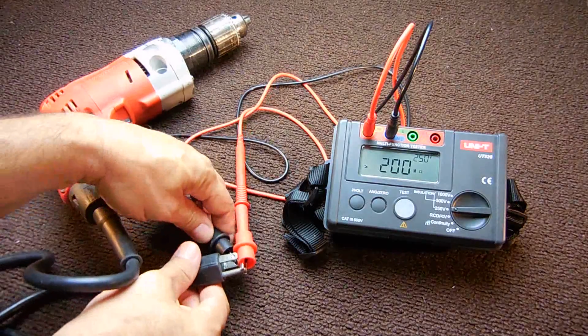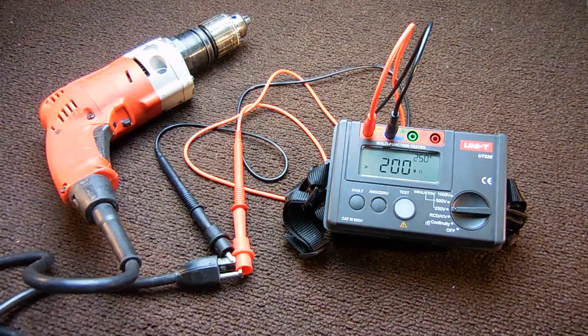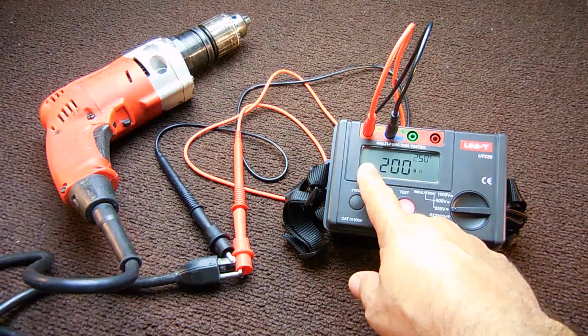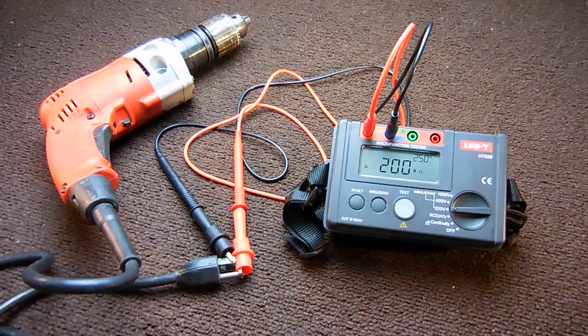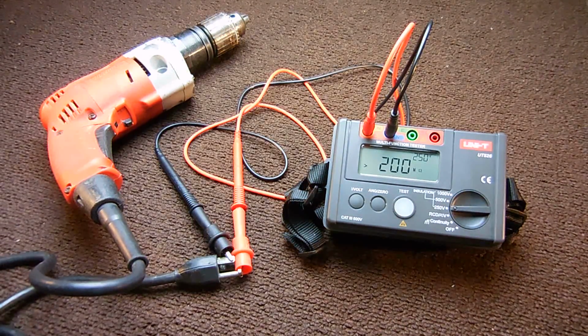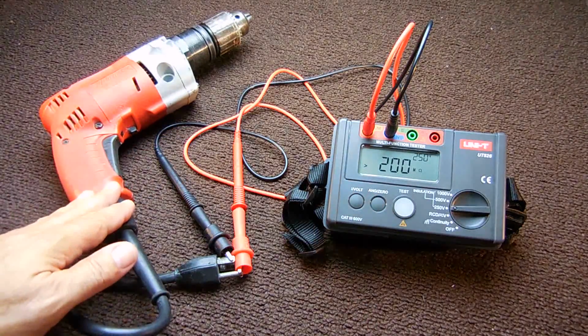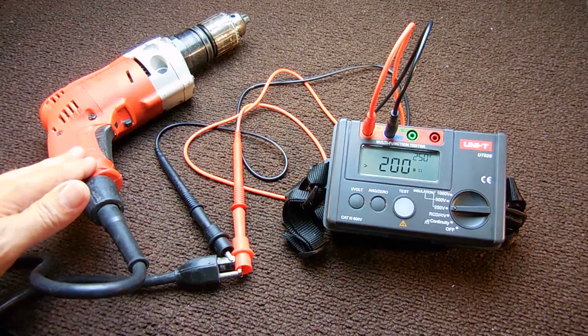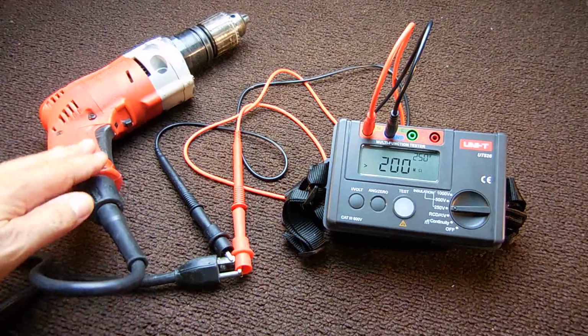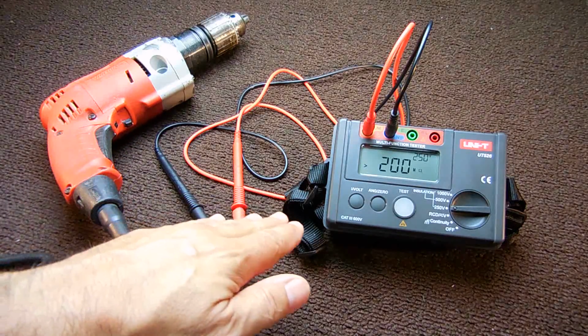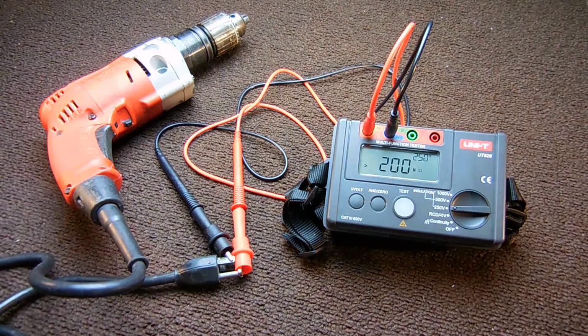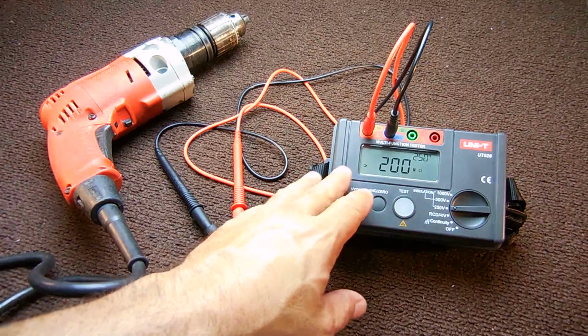Then you could flip it around this way, take that, move it to the top, and repeat the test again just to make sure. There, it's active, and it's still the same. The best way to establish what a good reading or a normal reading is, would be to compare this reading to a new drill, or over time, every 6 months, take a reading from a new one, and see how it gradually drops and levels off. You want to do it over time. If you had to work on multiple AC systems in a building, then you'd be able to compare all the compressor values.